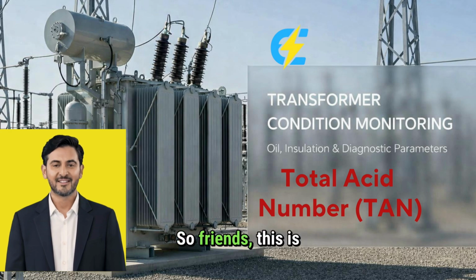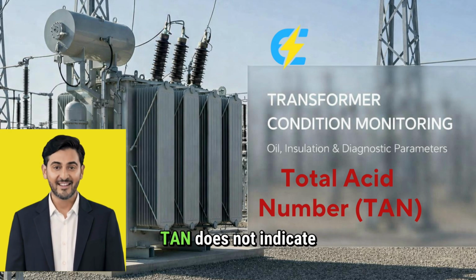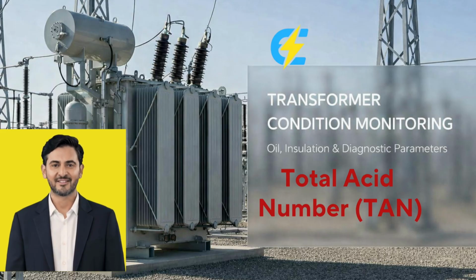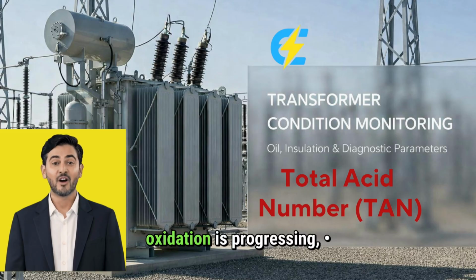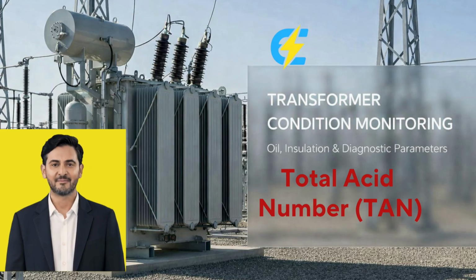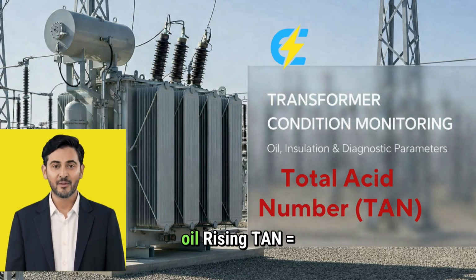So friends, this is the real meaning of TAN in transformer oil. TAN does not indicate a fault. TAN indicates chemical aging. It tells you oxidation is progressing, oil additives are exhausted, paper insulation is under chemical attack. Remember these rules forever. Low TAN, healthy oil.